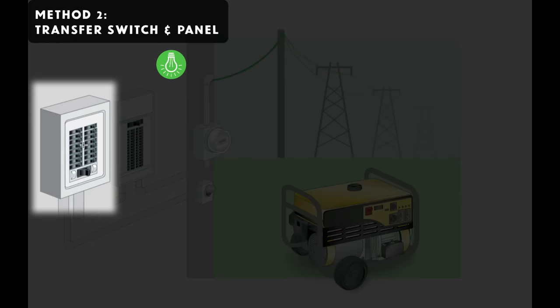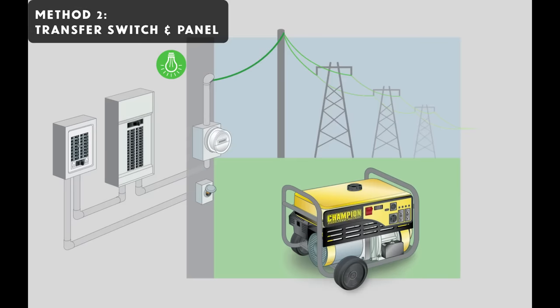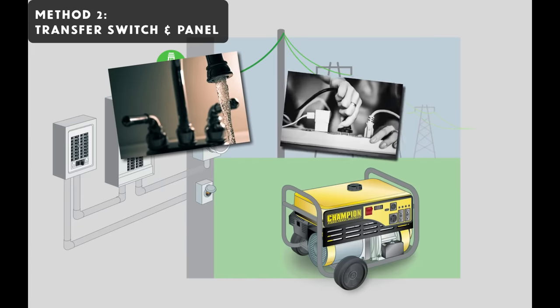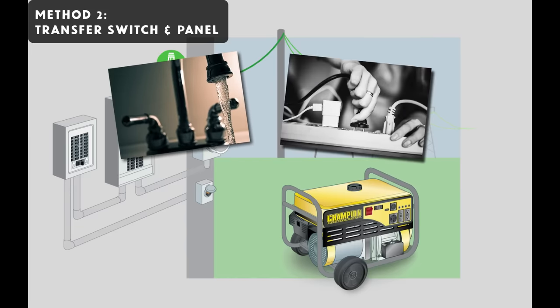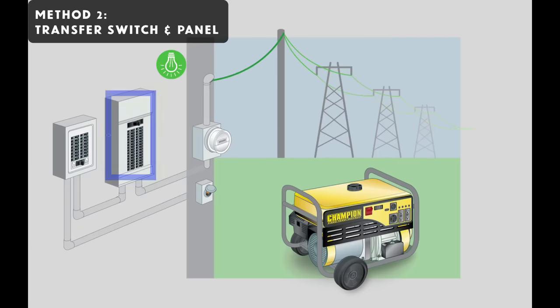This is something that will allow you to plug in a cable that connects the port and your electrical system to your generator. The second thing that needs to be installed is the actual transfer panel, and that's what you see here. Part of the installation process involves identifying essential circuits that you want powered during an outage. A portable generator probably can't power all the circuits in your home, but it doesn't really need to. You'll want to power things like a water pump, some outlets, some lights, maybe a furnace circuit, things like that.